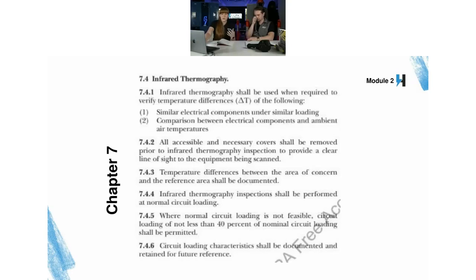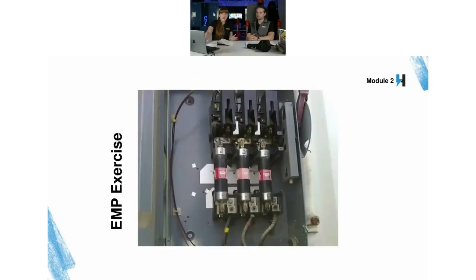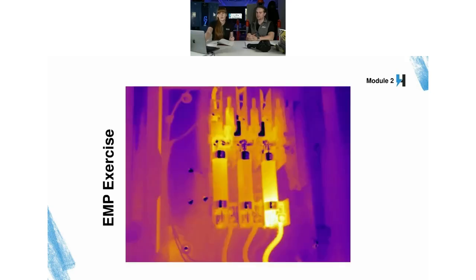So for this example, we have our fuses here, and there's the scan of them. Before, just from a visual inspection, we saw some discoloration on the C phase at the bottom right fuse knife clip connection point. Now we can see from the infrared scan at the bottom right, because it's brighter, it tells you it's hotter with respect to the rest of the image, there's probably a high resistance connection there. So a typical recommendation is to de-energize, take the fuse out, clean the clip, and clean the knife connection point there, and rescan to make sure that helped alleviate any heating issues. You can also see some heating in the top left on the A phase as well. So you'd want to check that same recommendation as well.